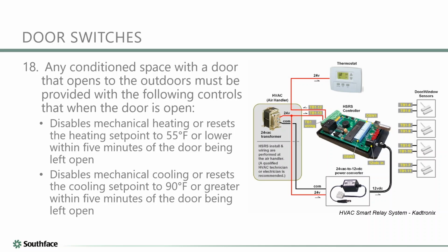The outside doors are open for a long period of time. They're letting in a lot of that outdoor air, so you basically turn off the heating and cooling at that time. So here is a system. I'm sure there are many different types of systems out there. But essentially, we don't want to be cooling the neighborhood, as my dad would say. So that's basically what this is about. And so keep that in mind. This is a requirement for the simplified approach.